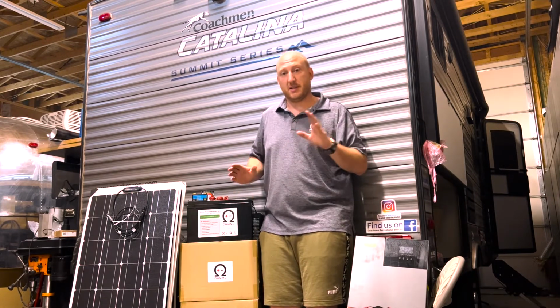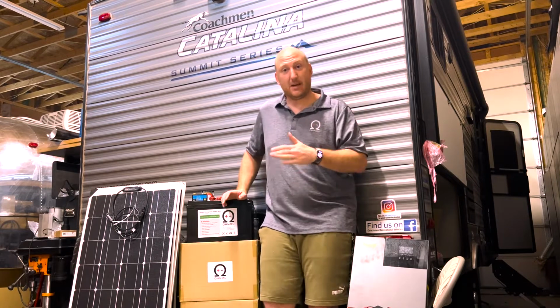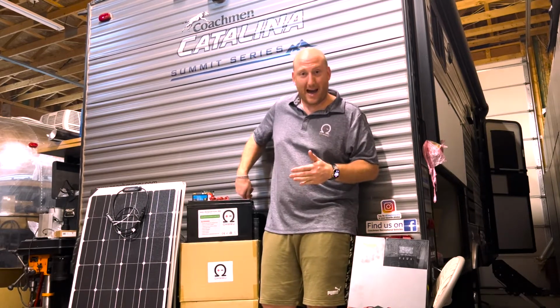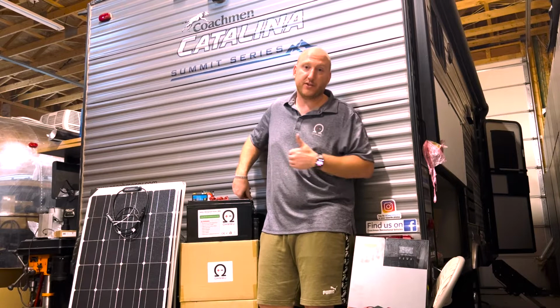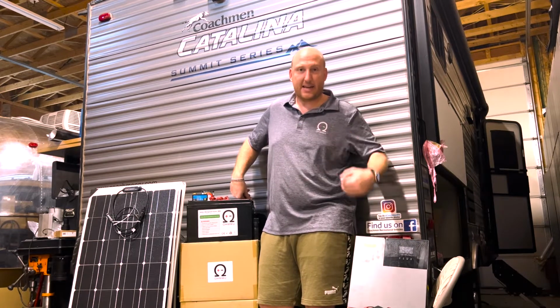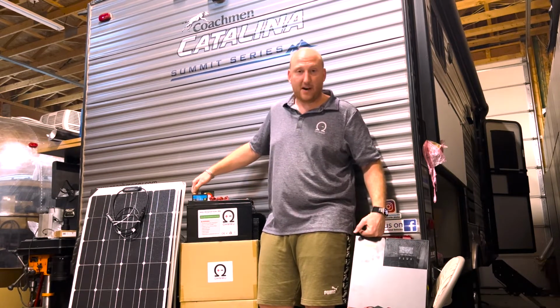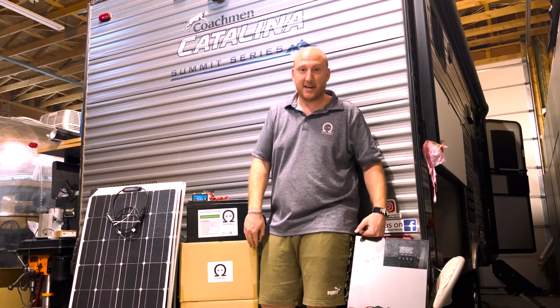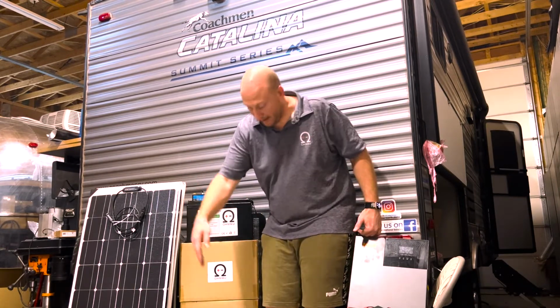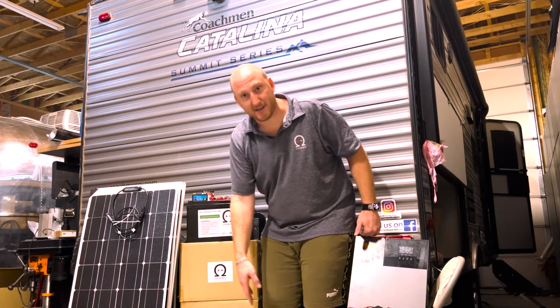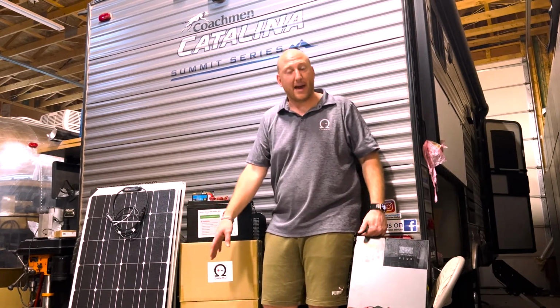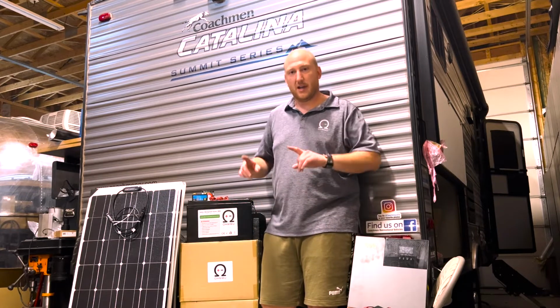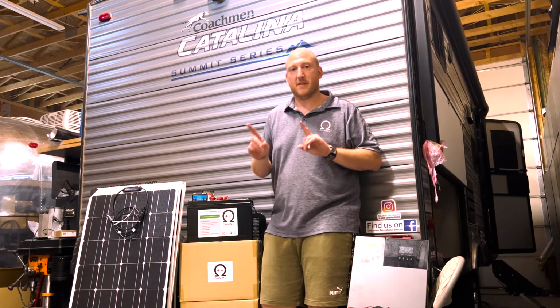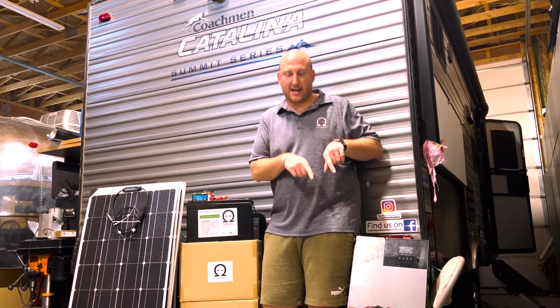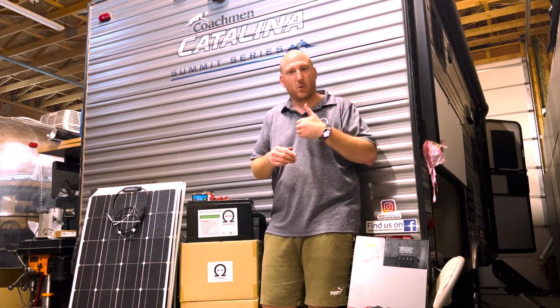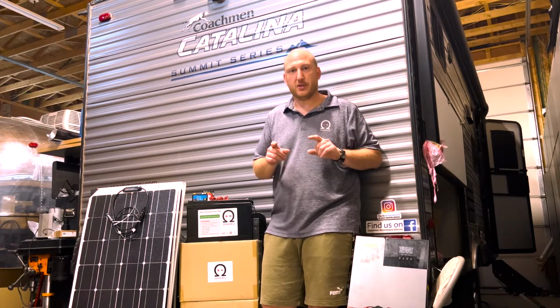That means we're putting 4 batteries in series wiring. The positive of one battery becomes the ultimate positive of the system, connecting into the system. The negative on that battery goes to the positive of the next, and so on - negative to positive - until at the 4th battery you have the ultimate negative. So you have one ultimate negative and one ultimate positive that go to the actual system. Because it's series wiring between that negative and positive, the voltage adds together.